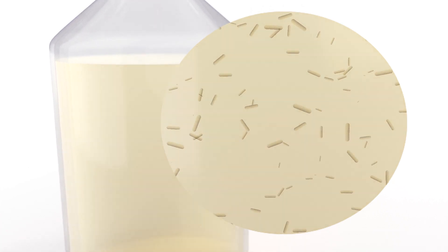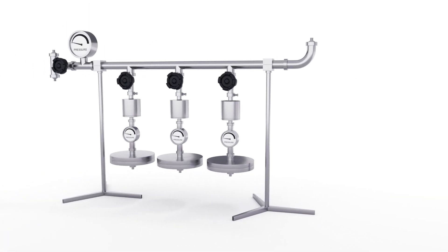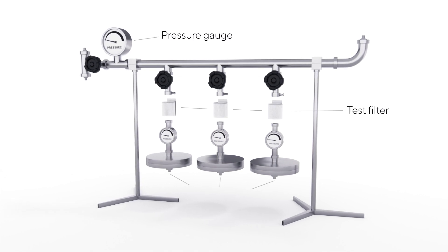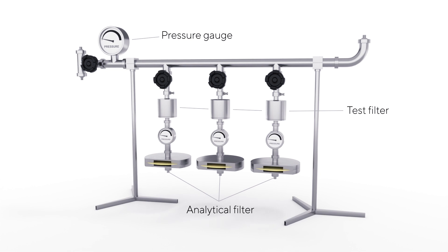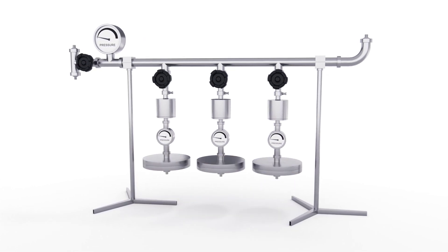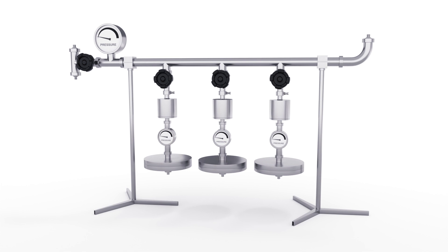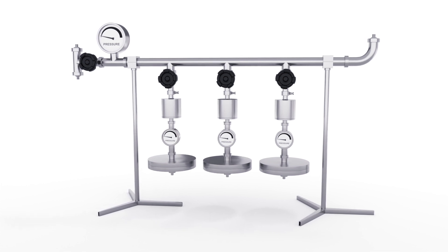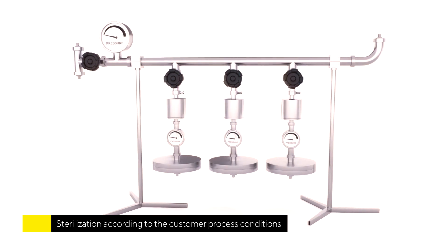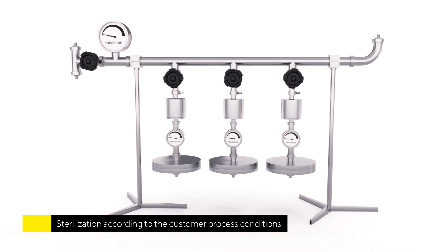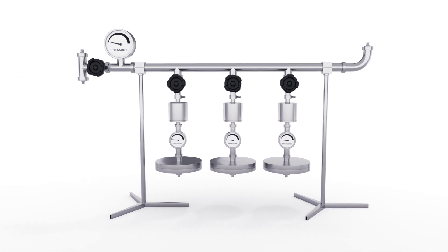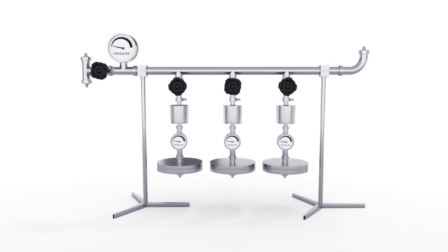For validation, three filter lots are considered. For resource efficiency reasons, all three pleated filter devices are tested simultaneously, enabling an automated and monitored test. The test setup is sterilised by heat, and the filters are sterilised according to the customer process conditions. Afterwards, the filter's functionality is verified by integrity tests.